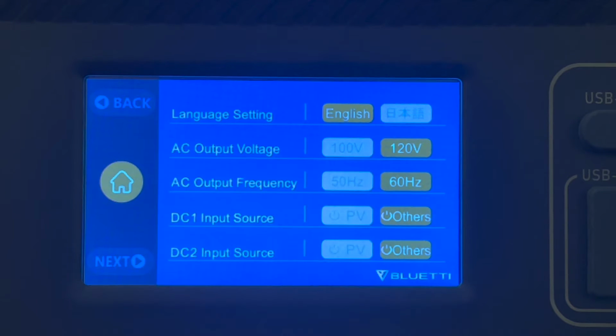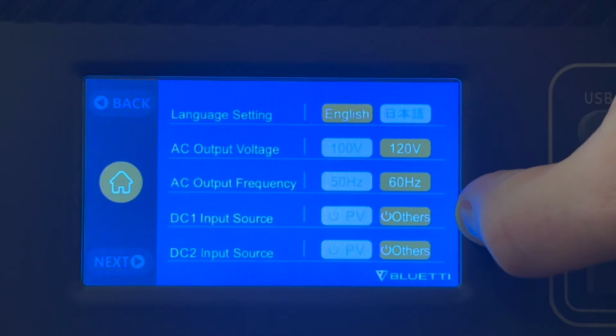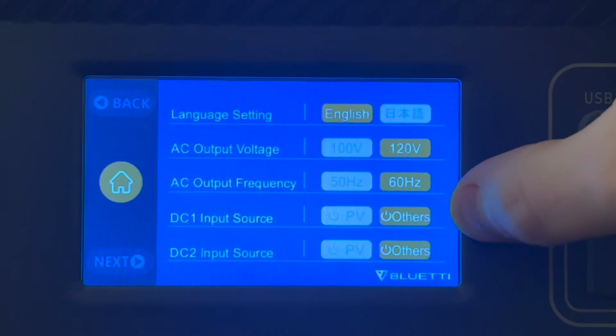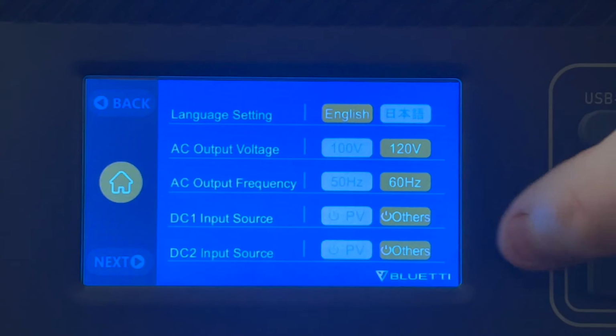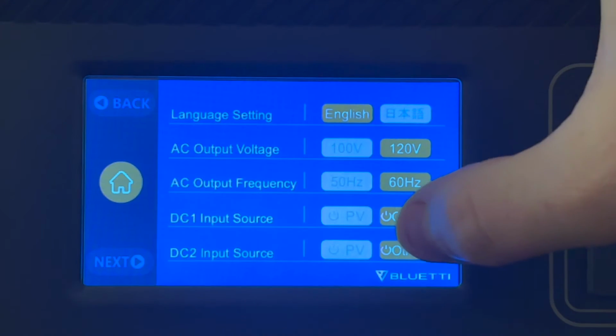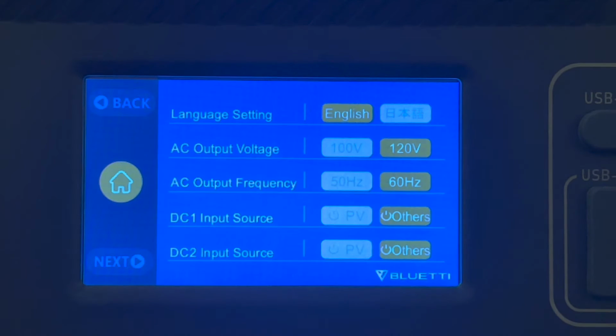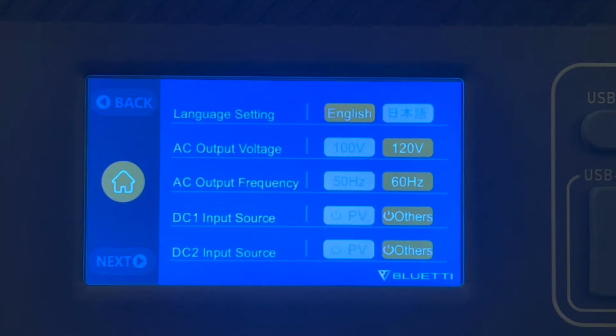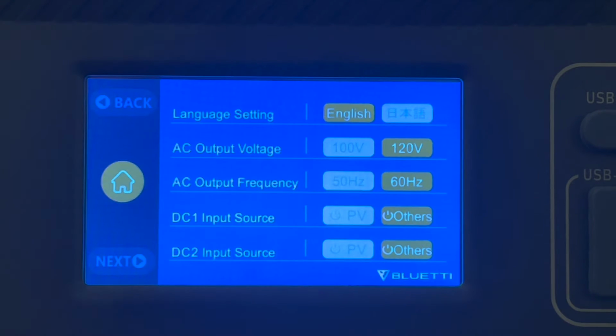You're going to need quite a bit of solar to keep this thing fed. But if you set it to others, one of the two things it will do is limit it to 10 amps. So you'll need PV if you're going to be pulling more than 10 amps. It does change the algorithm that the MPPT controller is using so that it behaves nicer if you're plugging in external batteries. It's going to be more of a constant type charge as opposed to trying to find that peak power mode.